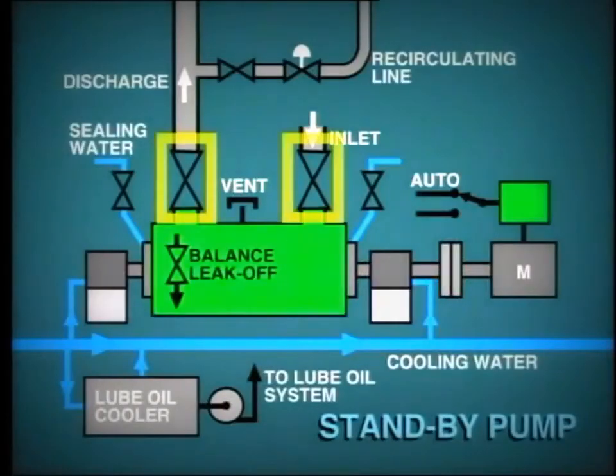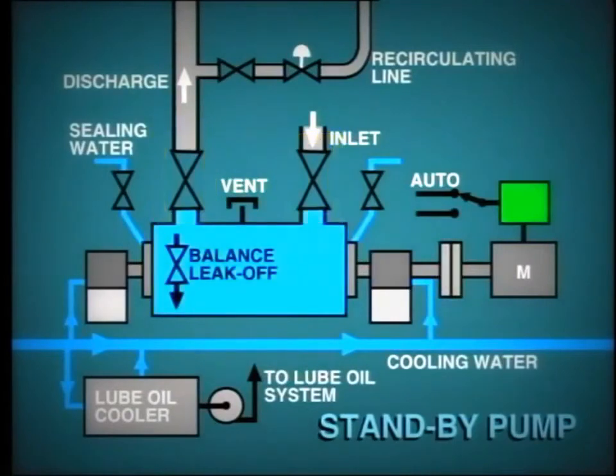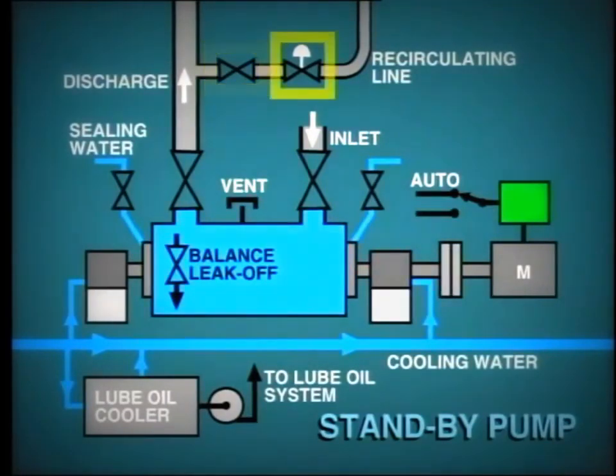The feedwater pump is truly the heart of the power plant cycle and therefore must provide 100% reliability in supplying high pressure feedwater. Make sure that you're familiar with all the mechanical details of your particular feedwater pumps and especially the procedures for making the pump available. For example, on the standby pump you will typically need to make sure that the inlet and outlet isolating valves are open, the pump is fully charged with water and all air has been vented, and the recirculating line isolating valves are open.